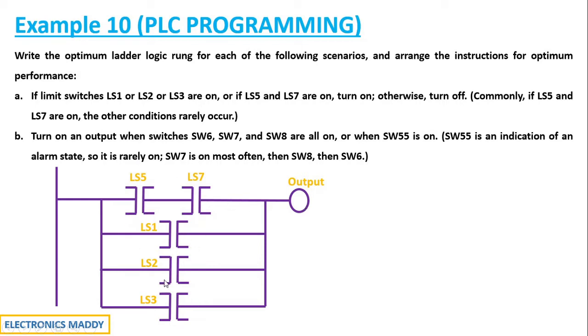If you place LS1 above, LS2 above, LS3 above and LS5, LS7 underneath, it has to go through each of the rung conditions to get the output. This is where we say we will be saving time by having LS5 and LS7 in series initially because they have already given that commonly, if LS5 and LS7 are on, the other conditions rarely occur. If this is on, other conditions rarely occur and we don't have to even check because this is OR operation.